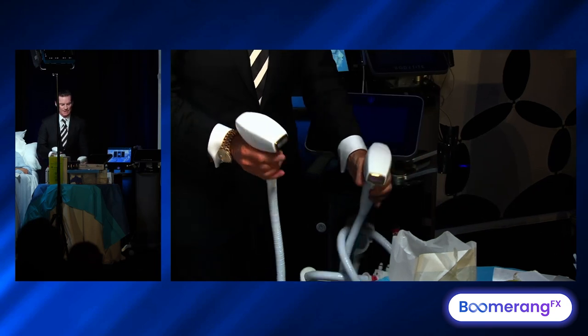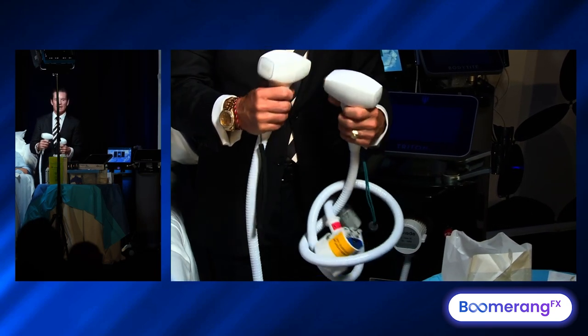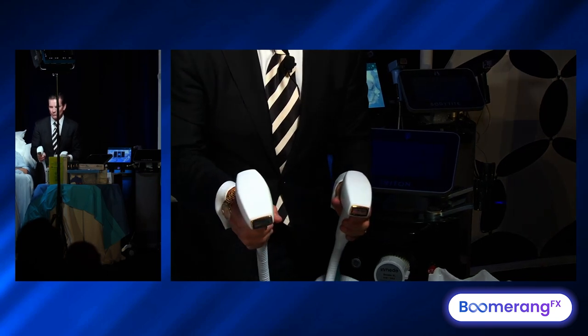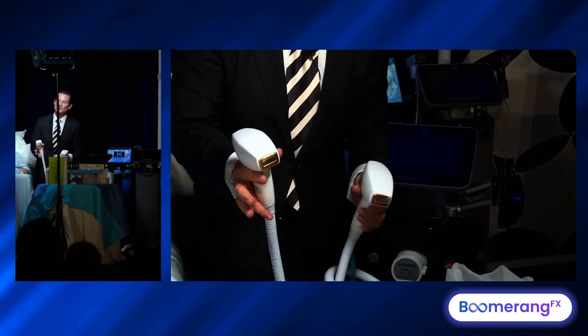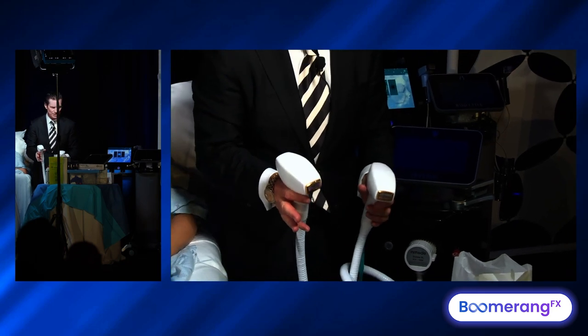You've got two options: what's called a duo light or a duo dark. The duo light is 755 and 810 in the same pulse — two photons sequentially pulsed. 755 gets the more superficial, smaller follicles. 810 gets the deeper, bigger follicles for skin types 1, 2, and 3.